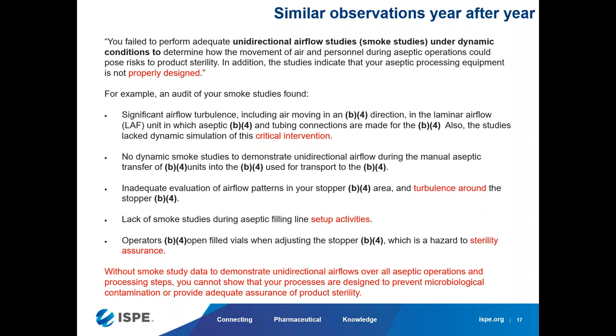Inadequate - I'm not going to read through everything, but in short what they're saying is we are seeing turbulent air. Turbulent air is fine in grade B, but grade A needs to be unidirectional, not laminar. There's a big difference. Without a smoke study to demonstrate unidirectional airflow across all aseptic processing steps, you cannot show that your processes are designed to prevent microbial contamination.